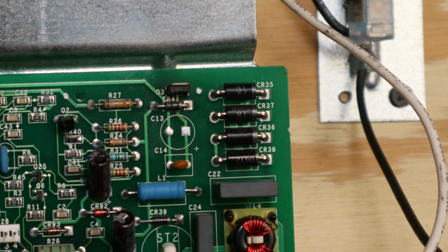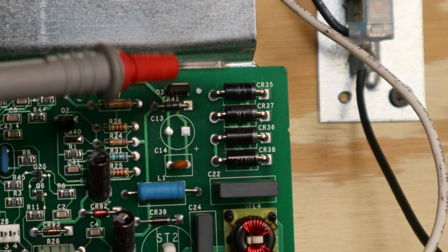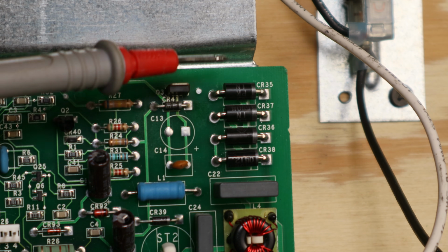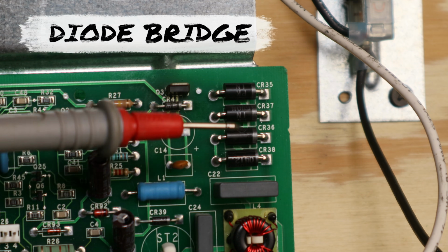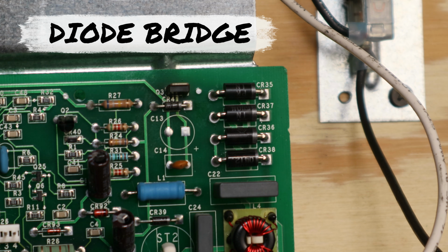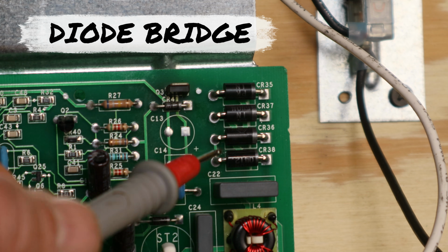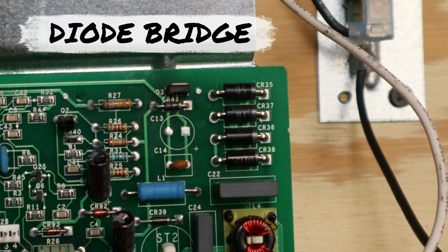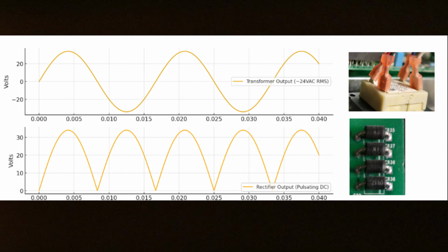Now, this is where things really change when it comes to the ECM motors and control boards versus the old stuff we're used to seeing. So you see these 4 diodes here. This is a diode bridge, or a rectifier. It takes the 24 volts in the control board and sends it through these diodes to turn it into a DC voltage. When our transformer is putting out 24 volts, it does it in a sine wave.